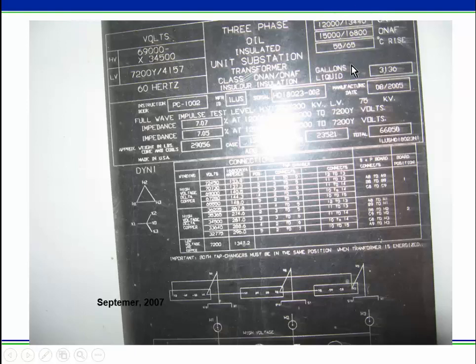So we'll do more of this in class, but for instance, if you have oil natural, which it always is, it just flows, there's no pumps on this transformer, and air forced, you could potentially put 16,800 kilovolt amperes through this transformer, and you would expect the windings at that point to increase in temperature by 65 degrees, and we assume an ambient of 40. 40 plus 65 is 105, so with 16,800 kVA on and the fans going at 40 degrees ambient C, we'd expect the windings to be at 105 degrees C. 100 degrees is kind of considered when insulation is golden, and above that we could start to lose a little life. So you could choose to operate this transformer a little more conservatively and put a little less load on it, and this would be your temperature rise, and you'd be under 100, right? 55 plus 40 would be 95.